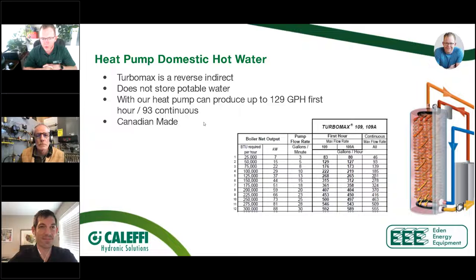So you want to do a reverse indirect. If you were looking at doing a 65 gallon reverse indirect, like a TurboMax, for example, you could produce up to 5 gallons a minute continuous at 60,000 BTUs. So that's pretty significant a draw that you could have on that. But again, you do not want to be doing a heat pump with a domestic hot water load without a design. This is not a matter of, oh, I don't think the heat pump's going to do it, so I'm going to put an 80-gallon indirect on it. Well, at that point, you've just given them a very expensive indirect that won't work versus a cheaper indirect that won't work.